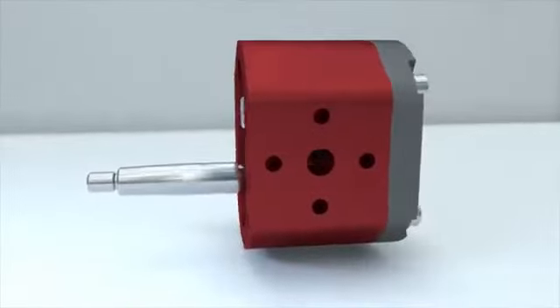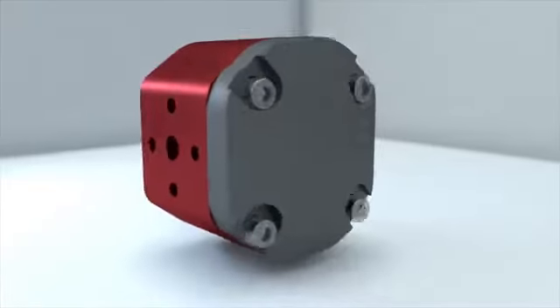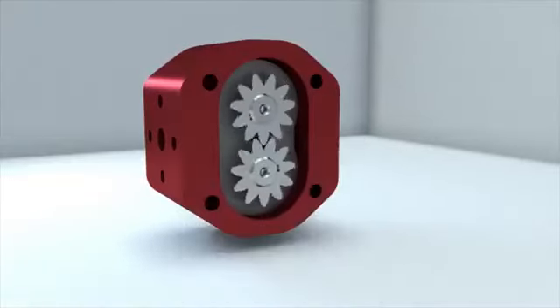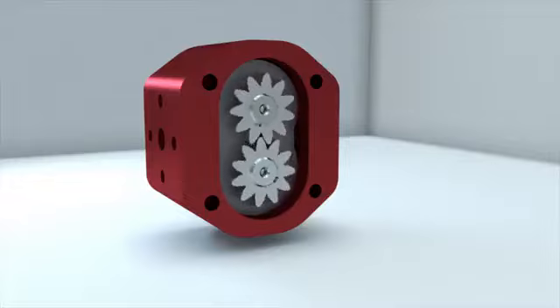Therefore, lobe pumps use an additional gear train, which is located outside the working chamber of the pump. This complicates the design, but with the same dimensions, lobe pumps can provide greater flow than gear pumps.